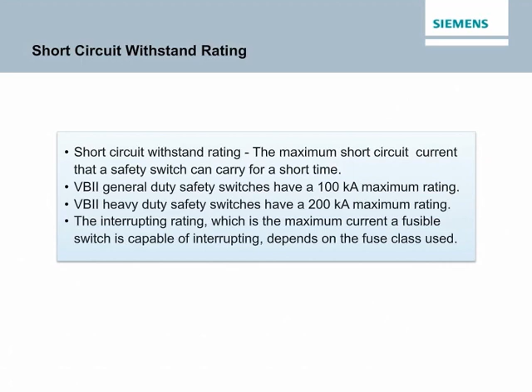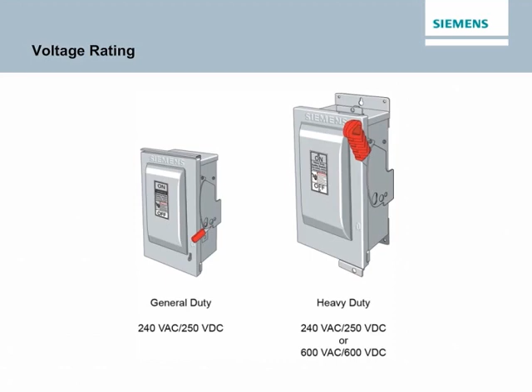Safety switches are also rated according to the maximum voltage they can handle. The voltage rating of the switch must be at least equal to the circuit voltage. In other words, it can be higher than the circuit voltage, but never lower. For example, a safety switch rated for 600 volts can be used on a 480 volt circuit, but a switch rated for 240 volts must not be used on a 480 volt circuit. The accompanying illustration shows the available voltage rating for Siemens safety switches.